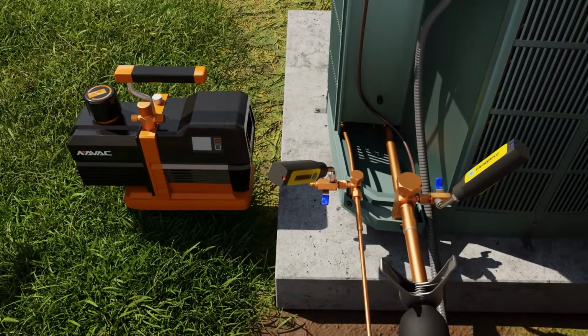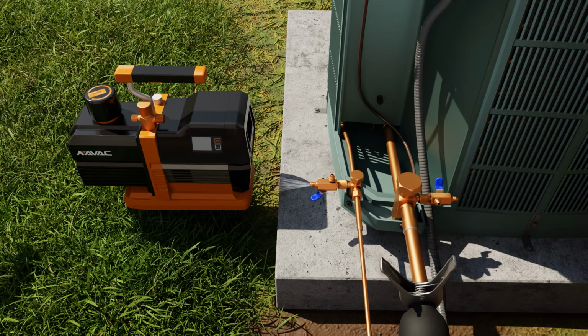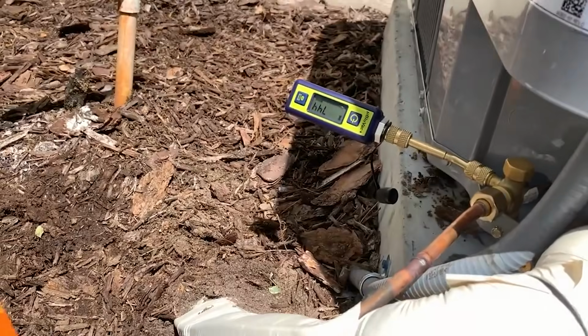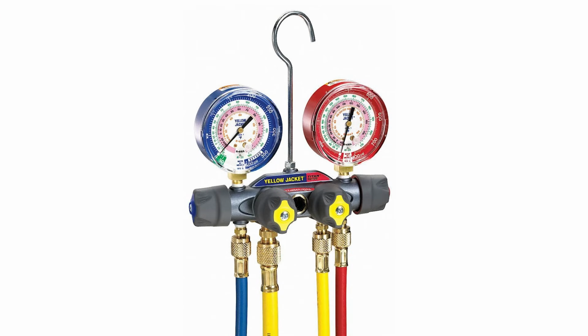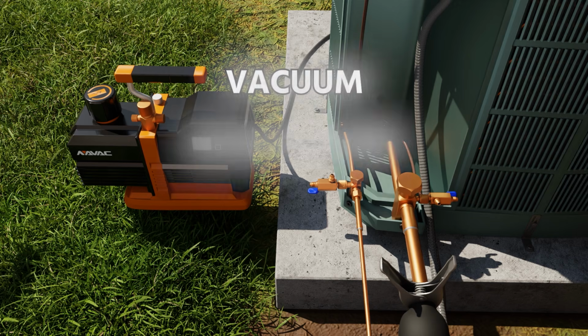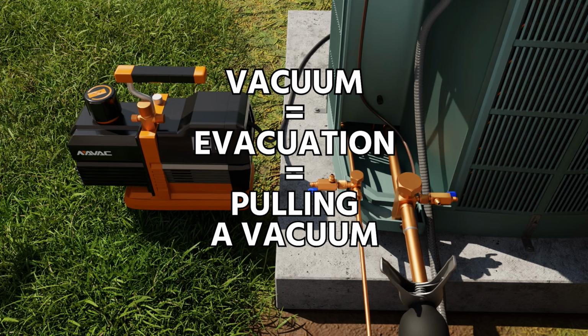A good nitrogen pressure test on a typical residential system will generally take about half an hour to prove no leaks if you're using a high-resolution pressure gauge. If you're using something like an analog gauge, it can be much more difficult, and it's much more likely that you will leave a leak just because you don't see that small change in the needle. First off, vacuum is often called evacuation or pulling a vacuum.